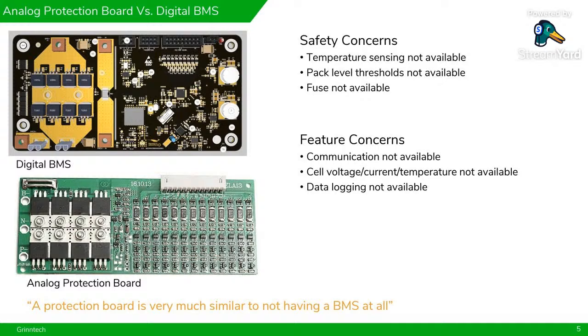If you observe that image, you can see lines of components, right? There's a big resistor on top, then some resistor capacitors, some small ICs in a line. Those are individual lines - if you have a 16 cell in series BMS, there will be 16 sets of that. All those components, including the IC, are doing only three things: cell over voltage protection, cell under voltage protection, and cell balancing. That's all, nothing else. There can be a short circuit protection too, since on the top left there's something that looks like a shunt. So: over voltage, under voltage, short circuit, and balancing.